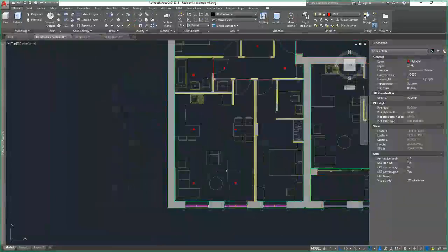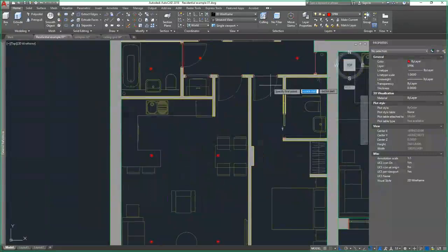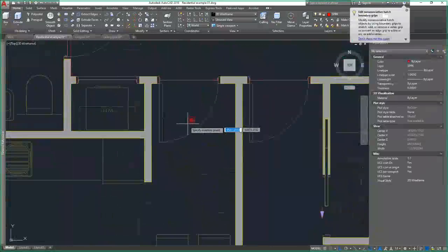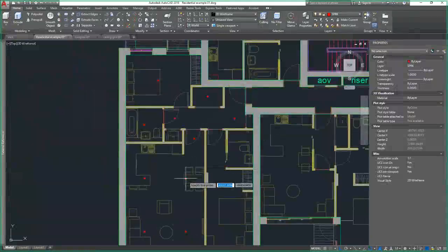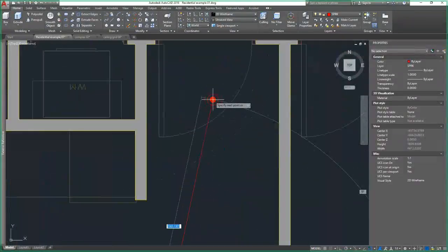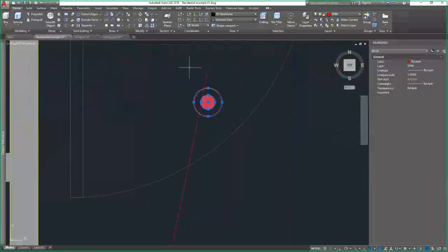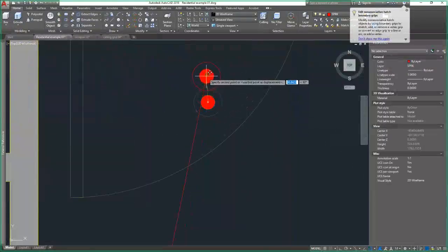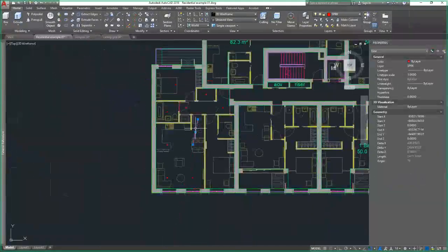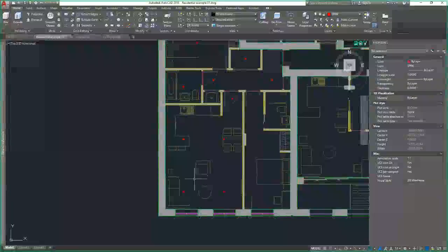The spacing's still good. So now, obviously I would normally place this central to the wall, but just to save time, let's just pop it somewhere there. Then we can check again. And what we got here, yeah, it's just under 2.4. So I just need to move that up a little bit more. There we have it. It's over 2.4 meters. So for me, that is a sensible way of arranging the heads.